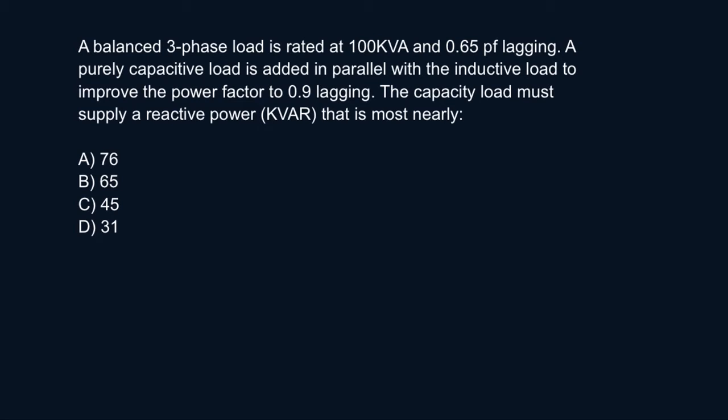So because majority of loads are essentially inductive loads, they're inductive, you need some sort of reactive power in order to make it work. So that reactive power is provided by your capacitor. So the question here, you have a system, 100 kVA 0.65 power factor, you need to bring that power factor up to 0.9. So you add a capacitor in parallel with that load. And the question is asking you how much is that capacitor contributing as far as reactive power.